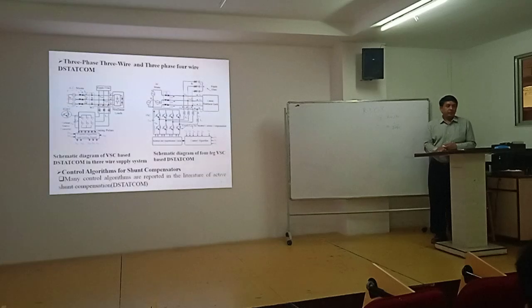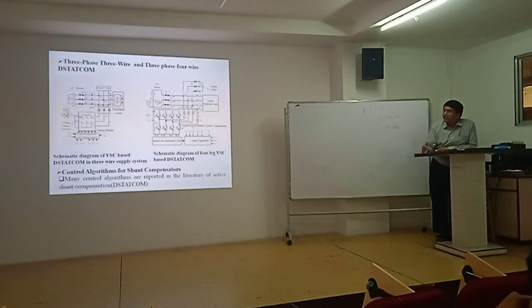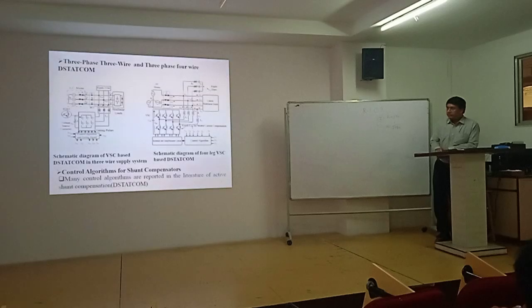So, if our switching frequency is 10 kHz, this filter provides a low impedance path for higher switching noise across 1 kHz, 2 kHz, 3 kHz, 5 kHz, 7 kHz. But theoretically, this is more effective after half of the switching frequency, meaning it works better for switching frequencies above 5 kHz. Clear?